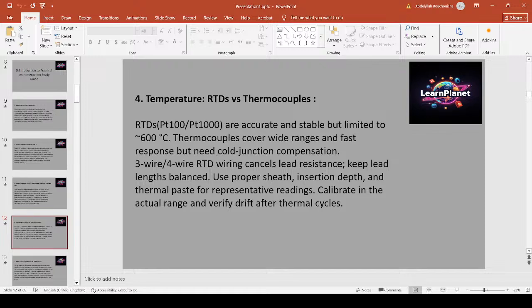Temperature: RTDs, thermocouples. RTDs, Pt100 and Pt1000, are accurate and stable, but limited to about 600 degrees Celsius. Thermocouples cover wide ranges and respond fast, but need cold junction compensation. 3-wire and 4-wire RTD wiring cancels lead resistance. Keep lead lengths balanced. Use proper sheath insertion depth and thermal paste for representative readings. Calibrate in the actual process range and verify drift after thermal cycles.